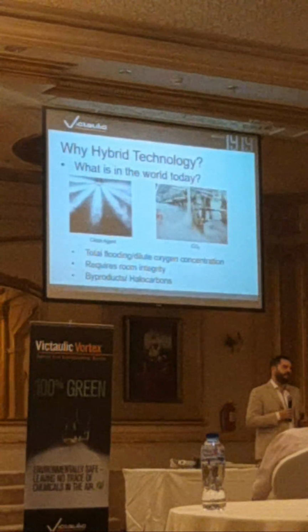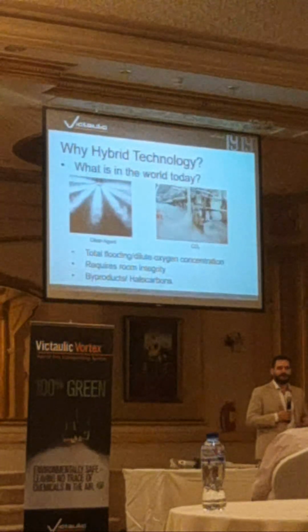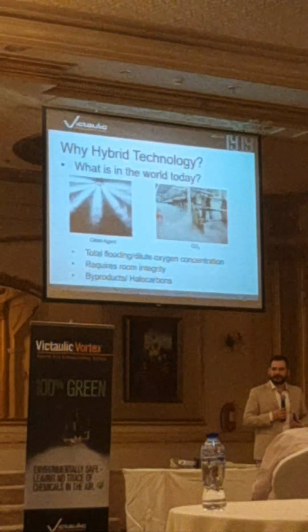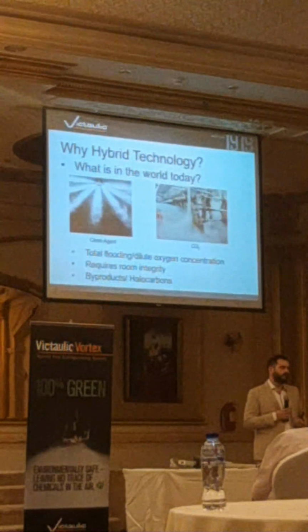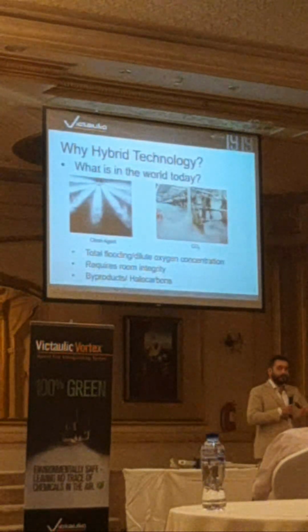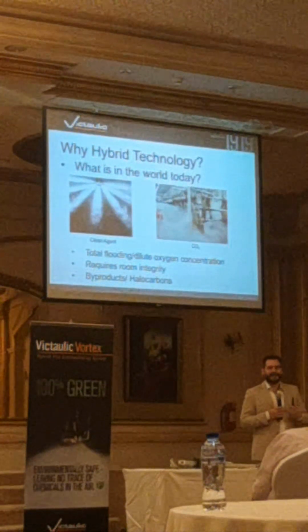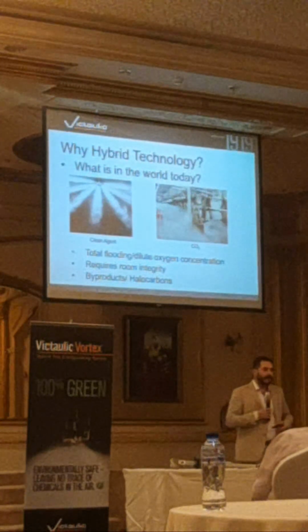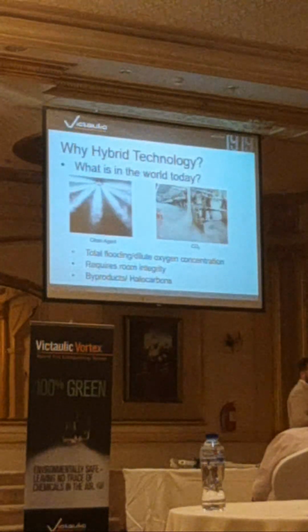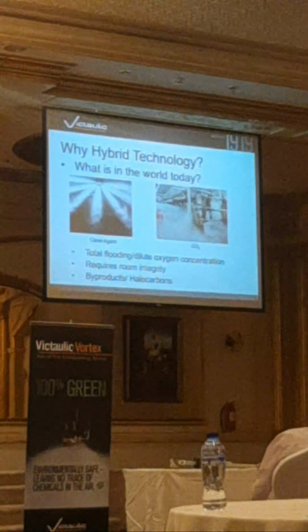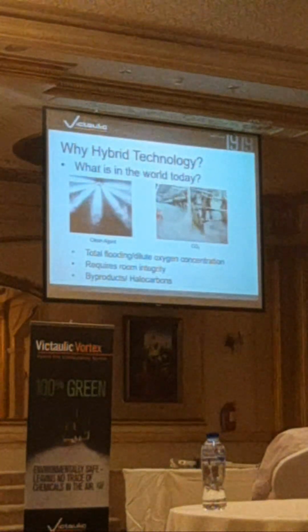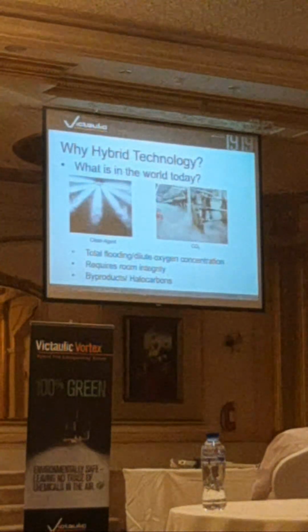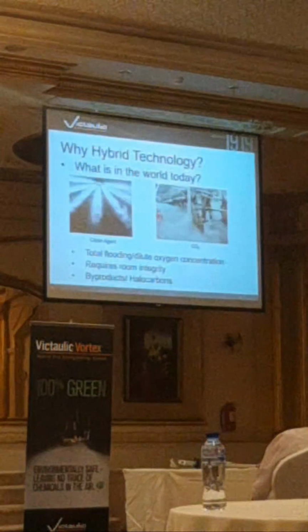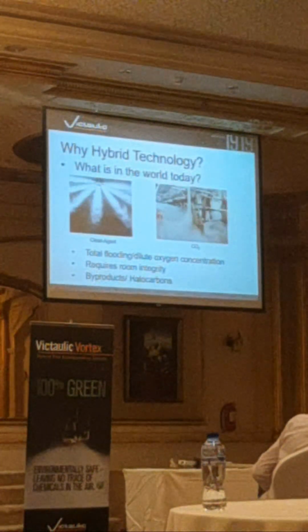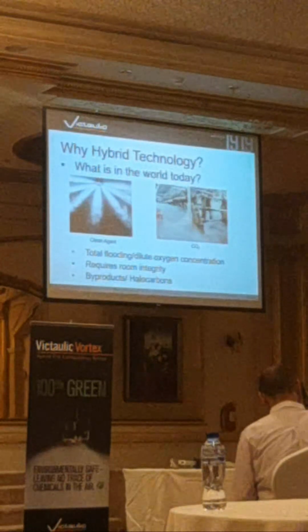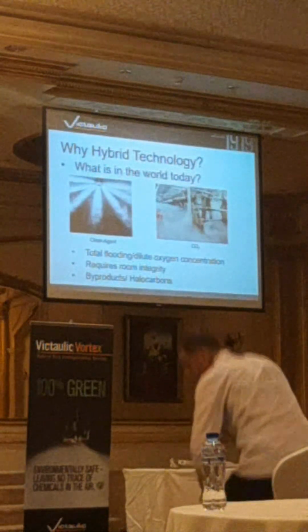The big thing for an FM200 or a Novec or any sort of gaseous system is that you need to have a sealed room. You need to make sure that your complete room is sealed so that the gas doesn't escape somewhere. And to do this, you need to have a construction cost, and also because you're sealing the room, you need to have the construction cost of pressure relief dampers to make sure that you're not damaging any equipment, or that potential people inside can still leave that area.